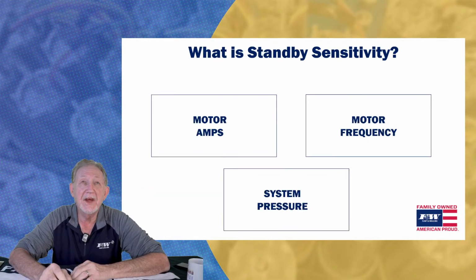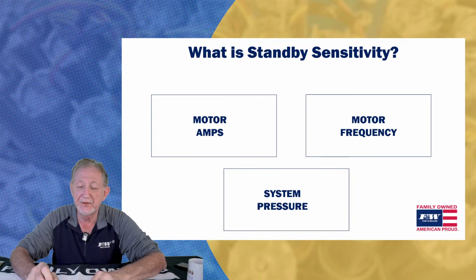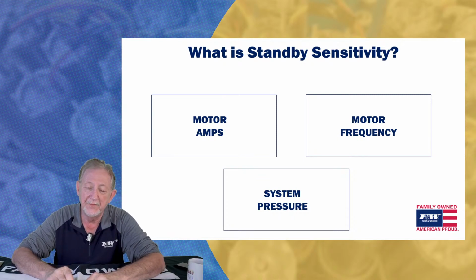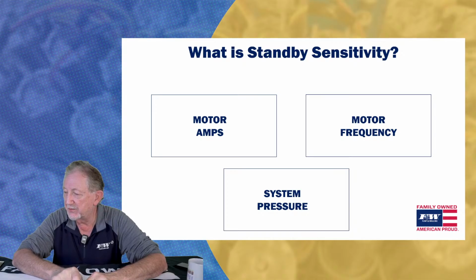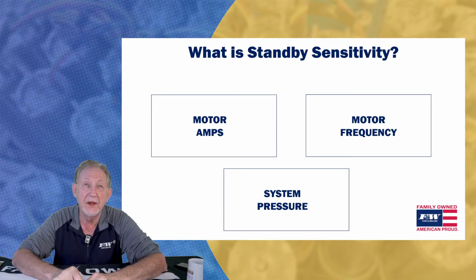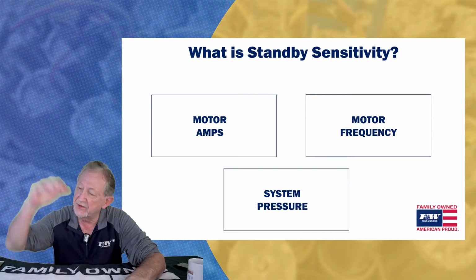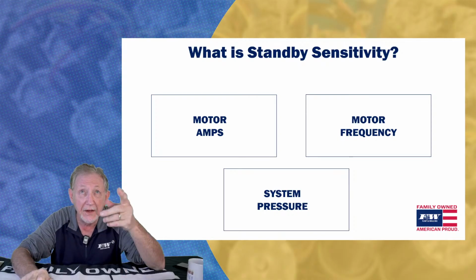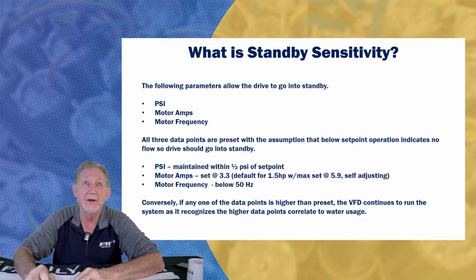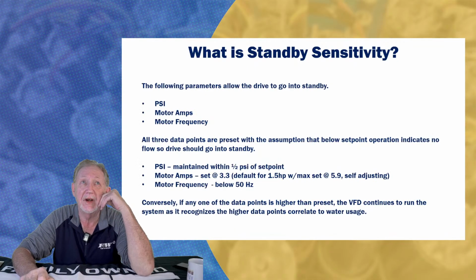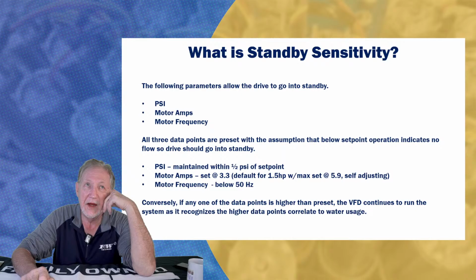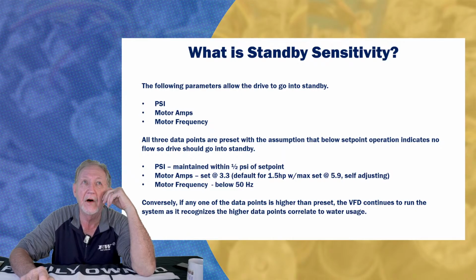All right, what is standby sensitivity? Now there are three measurables on the standby sensitivity. Again, what we just talked about with the underload, that's if you're running below that threshold on amps but the motor's running at full RPMs, right? So here, with standby sensitivity, there are three measurables: the pressure, the motor amps, and once again, the motor frequency. All three data points are preset with the assumption that below the set point, operation indicates no flow, so the drive goes into standby.